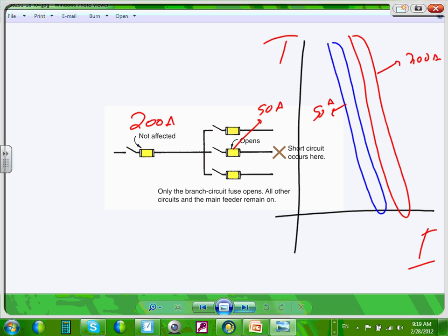That's it. If they touch each other at the bottom or anywhere, then they're not fully coordinated. They are coordinated, but not fully. What does that mean? Meaning, suppose the short circuit right at this point here, guys, goes to, say, 11,000 amp. At 11,000 amp, the big boy will trip.